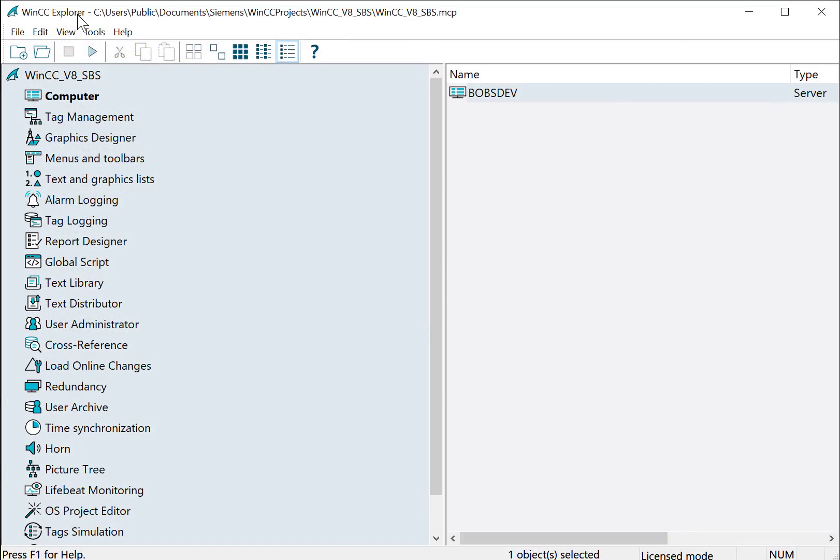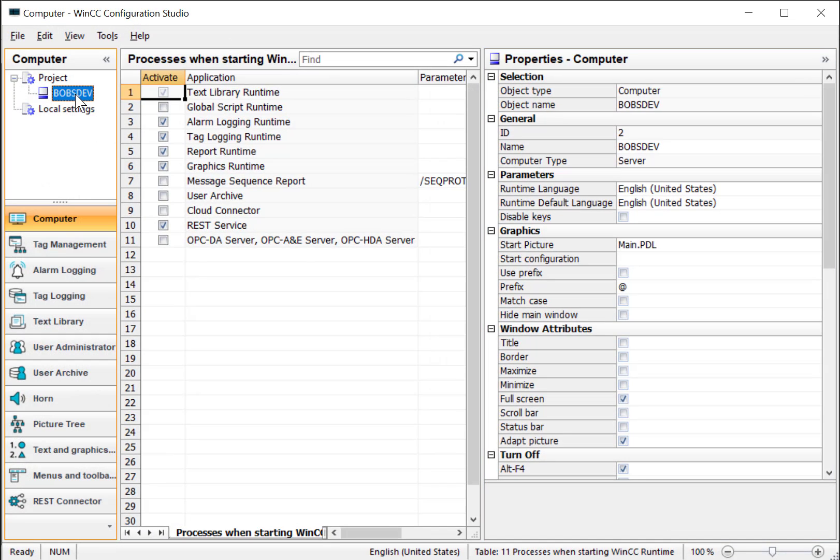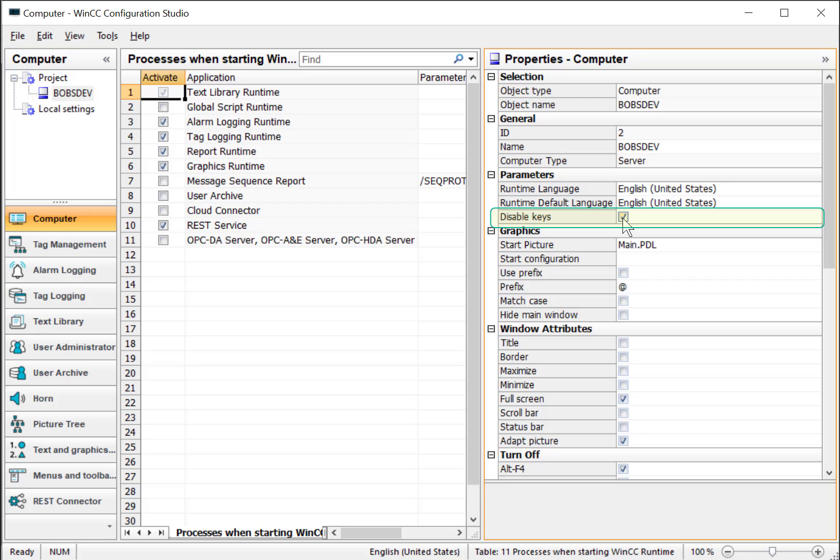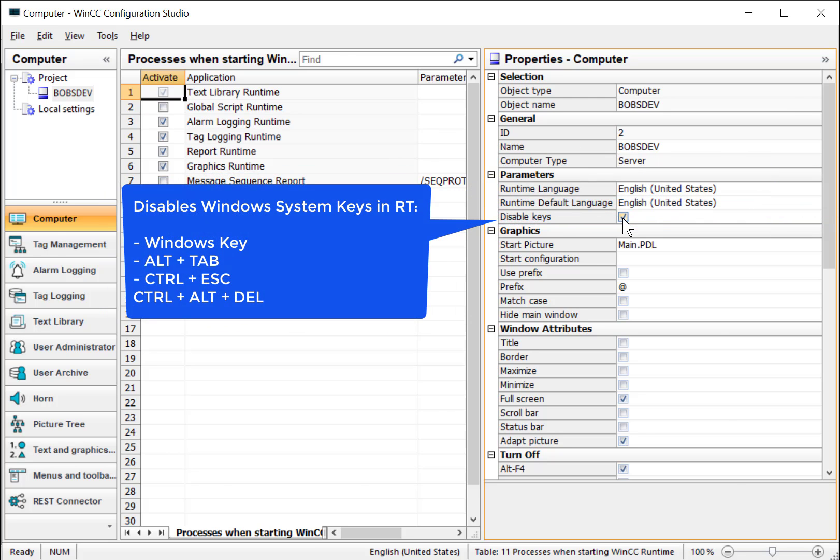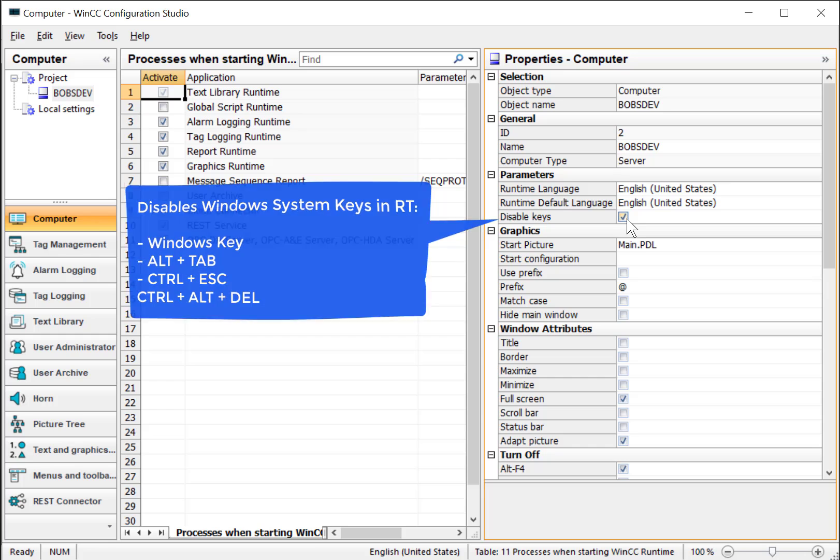Next, we're going to go to WinCC Explorer to secure the runtime project. We're going to double-click on the project server and we'll select the server. And under parameters, we're going to check disable keys. What this does is disables the Windows runtime keys that allow you operating access. This is like the Windows key, Alt-Tab, and Control-Alt-Delete. So this only takes effect when the application is in runtime.